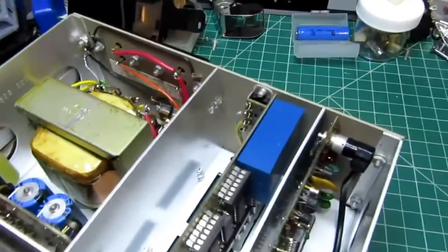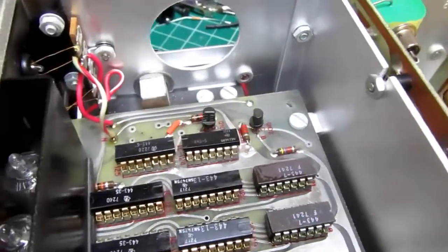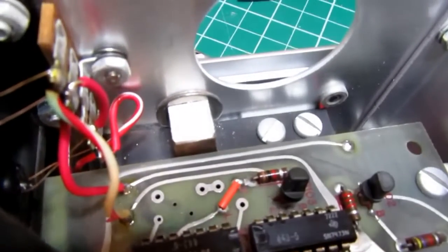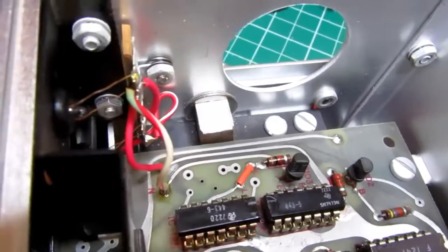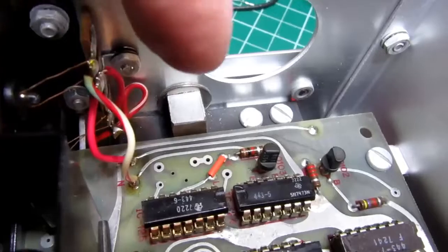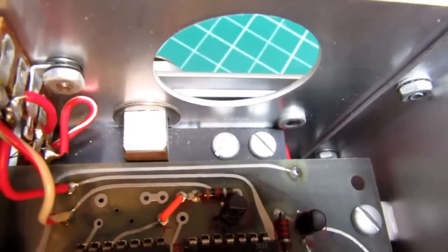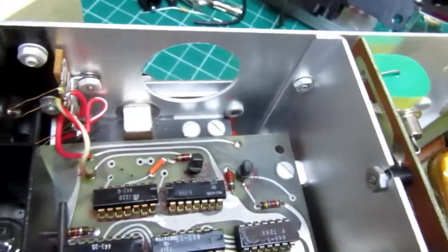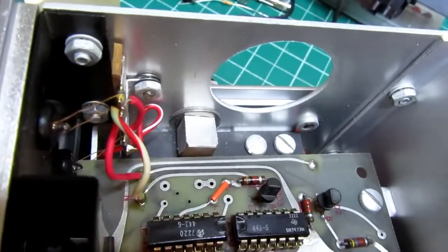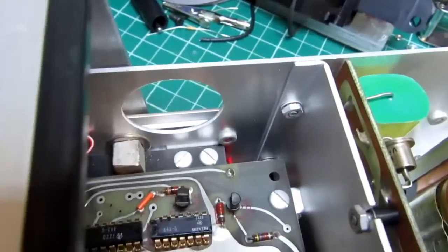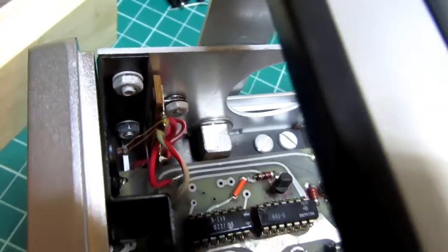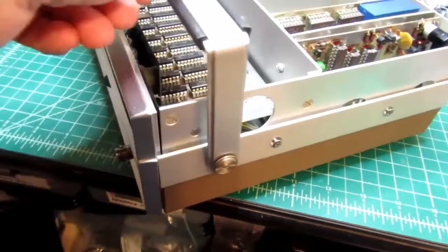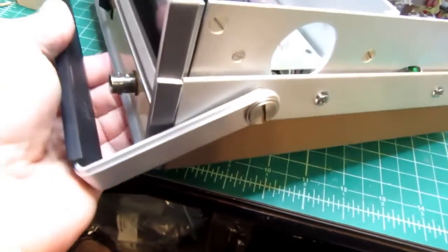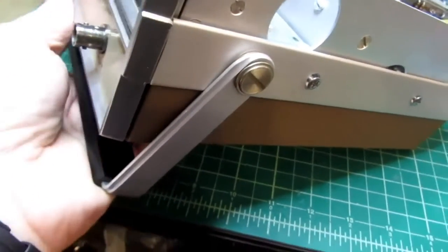I've reassembled the handle on there, and I should point out, I think I've kind of given this short shrift in my other videos. For example, on the IM-102 and the IB-1101, they all have this same kind of detent system, which is a little kludgy, not as nice as a professional meter would use, but still better than a lot of them. It just has on this one side a lug keyed to the handle. In other words, the handle is keyed to this lug, which can turn, and it has 4 flats, and then there's a leaf spring there, a piece of spring steel secured with 2 screws. And when you try to turn it, it deflects the spring so it doesn't want to turn until you get it to a certain orientation, which has to be 90 degree increments. So there's no in between if you want it to lock. But then it pretty much stays in that position. You know, it doesn't want to have other positions, but they're still useful positions.